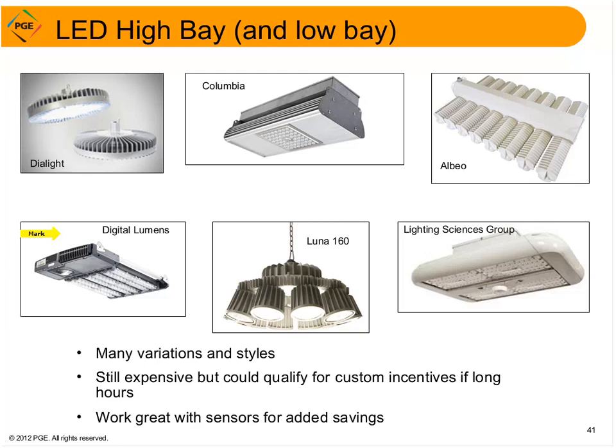So these fixtures come with a fixture-mounted occupancy sensor, and the LEDs come to full brightness instantly. So then after sensing inactivity, these fixtures switch off again after only, say, 30 seconds. Because people that work in a freezer don't want to be there very long. So in this way, even though you might be spending $700 for this fixture, it's hardly ever going to be on, and you're going to be saving 90% over a high-pressure sodium. And even though you're spending $700, this project has qualified for Energy Trust custom incentives.